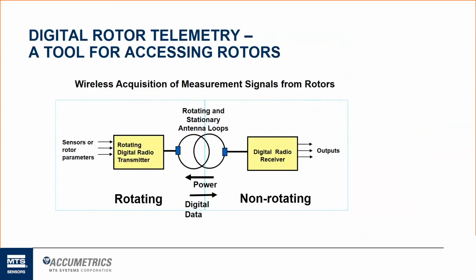So here's just a basic diagram of how it works. It's taking some type of sensor or rotor parameter, in this case, field voltage and field resistance. It takes that information into our rotor mounted transmitter, which is an analog signal. We do some analog to digital conversion. We transmit that signal through essentially a loop of wire. There are two loops of wire, one on the rotating world, one on the stationary world, that forms that rotary transformer and creates that communication link between the rotating part and the stationary part.